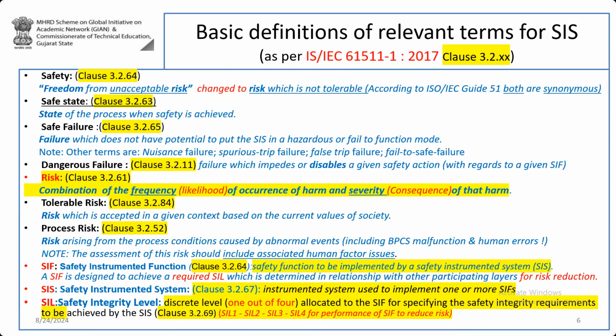Dangerous failure is the failure which disables a given safety action. That means the safety action will not take place if there is a dangerous failure of a device which is a part of the safety system. To give you an example, suppose you have a level transmitter and the level transmitter fails dangerously. That means you do not know whether it has failed or not. Had you known, you would definitely remove and replace the transmitter or repair it.